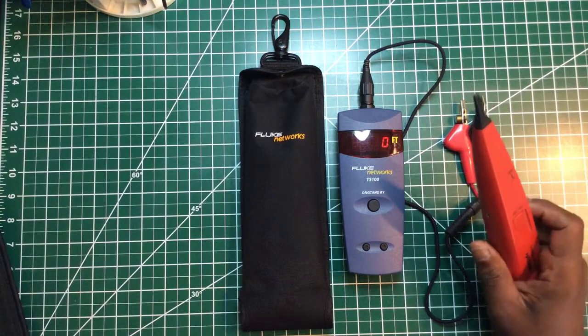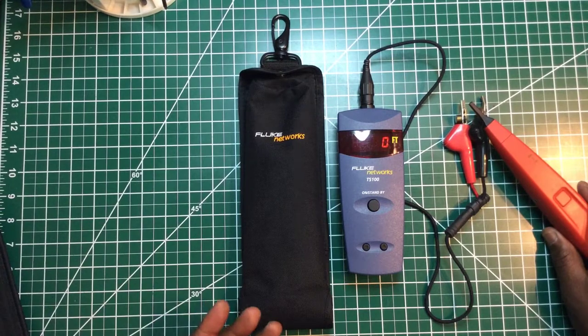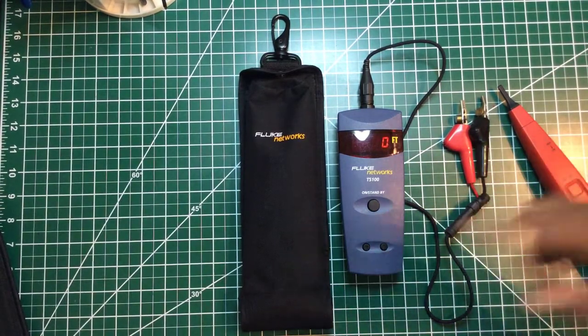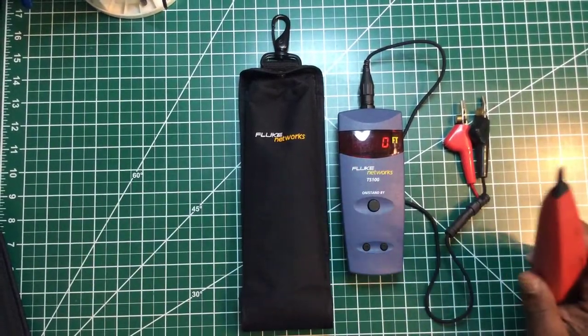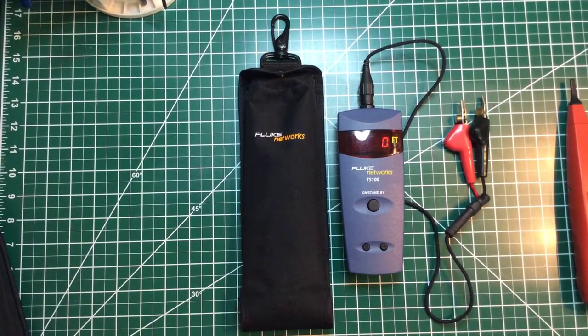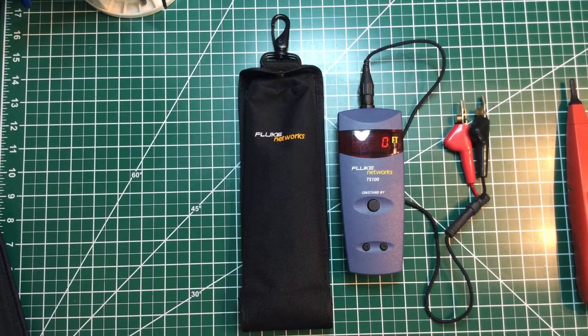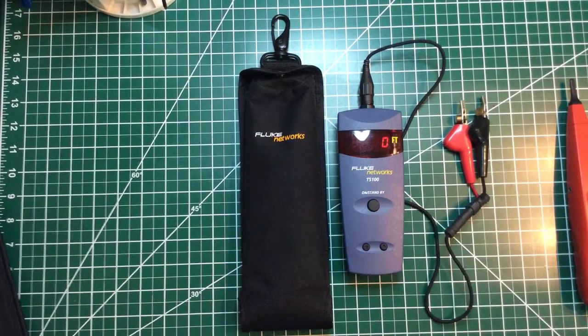I used this before when I was hunting down wires in machines, hunting down wires in pipes and panel boards, when conduit went this way and turned this way through a wall, and we found a panel board on the other side of the wall, and that wasn't it. But we went to each panel board all through the hospital where I was working at the time, and we located it. We can locate it with this tool. It must have been close to 1,000 feet, with all the turns and ups and downs. And this found it.